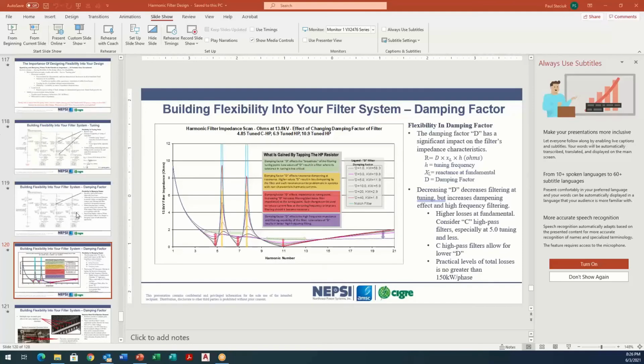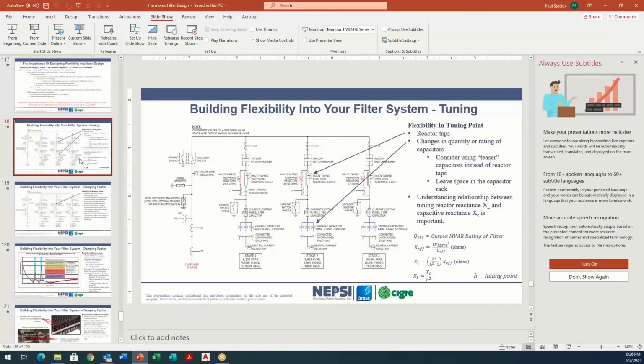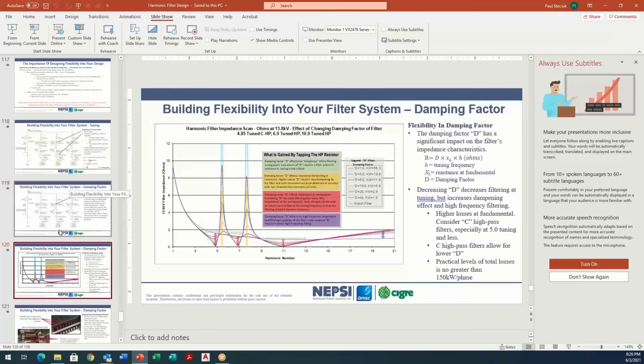Yeah. So the first thing to consider is what the harmonic current injection from the inverters is going to be, which is very low. My recommendation would be to go with a filter similar to what you see here, either a high pass filter or a C high pass filter, and you create an impedance profile that's very damped. So just a single tuned filter that's damped, meaning it's not going to excite or magnify harmonic currents because it creates a very flat impedance curve. C high pass filters and high pass filters, but especially C high pass filters that are heavily damped, are, I call them, almost a no-brainer solution. You're paying a little bit more for it, but you're not going to magnify currents at a frequency that you don't intend to, and yet you'll still get some filtering capability. So I would say lean towards a high pass or C high pass filter for renewables.